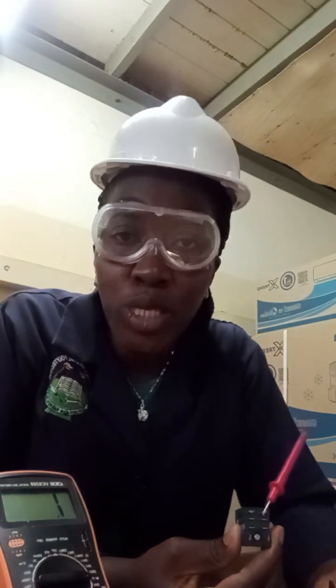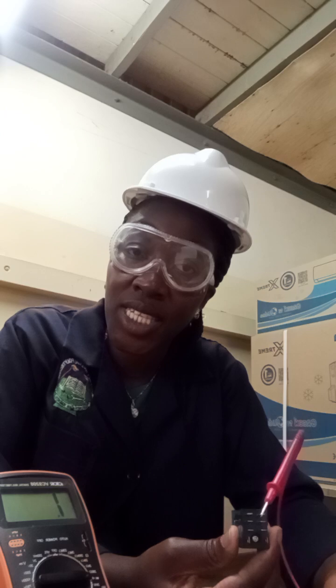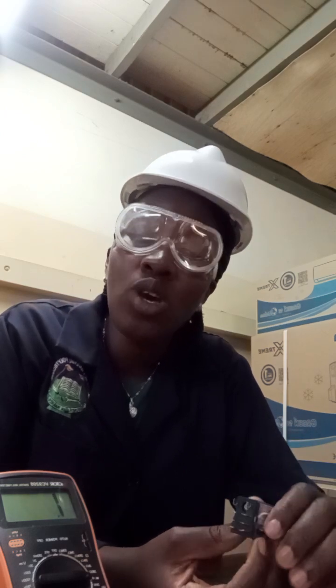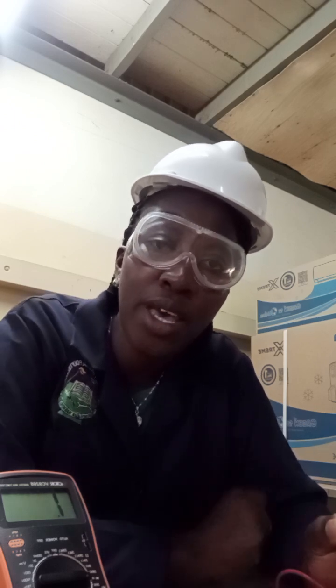The same case applies to our domestic fridges. Even in domestic refrigeration equipment, we always have the relay and the overload, and some will even have capacitors, both the start capacitor and the run capacitor. All these electronic components are connected to the compressor, so you have to check the resistance and even the continuity so you can tell whether it's working or not - whether it's in good working condition or faulty.